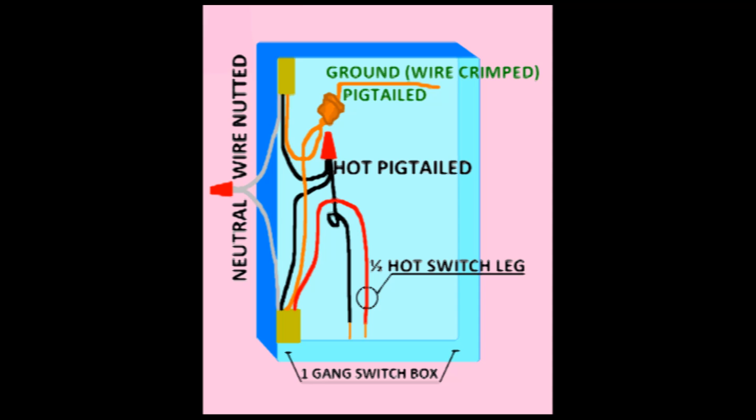Note in this diagram that the black wire is pigtailed and the white wire is wire nutted together. The ground wire is pigtailed using a copper ground crimp and that leaves your red wire from the 12-3 to be used as a switch leg.